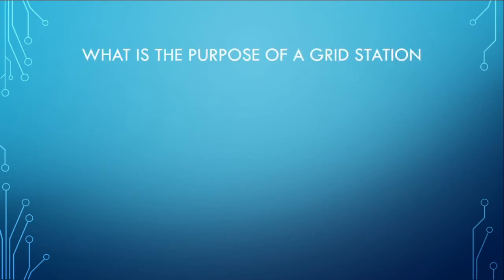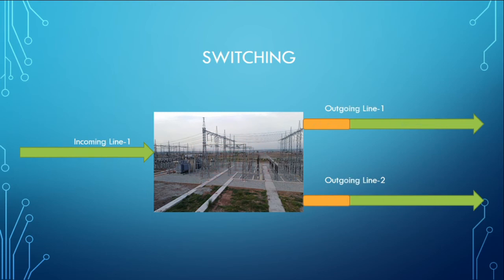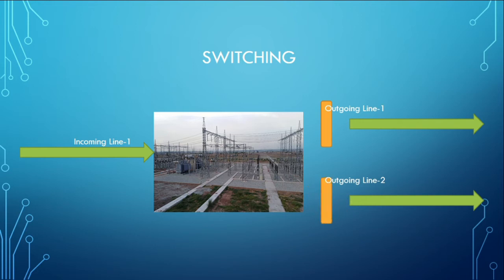There are two basic functions of a grid station: switching and control. One important function is switching — it means controlling on which lines we want the flow of electric power. For example, if we want to carry out maintenance work on outgoing transmission line number one, the line must be in the open position for safety, so we can open it from the grid station. All the power will then flow to outgoing line two. If maintenance is needed on both outgoing lines, we can open the second line from the grid as well. That is how the grid performs its switching function.